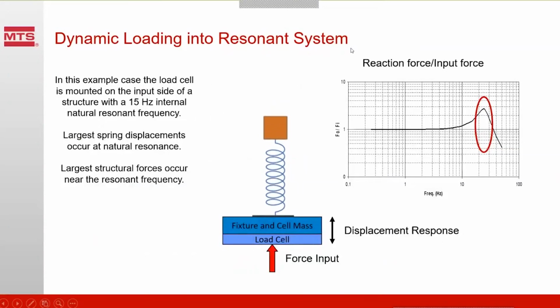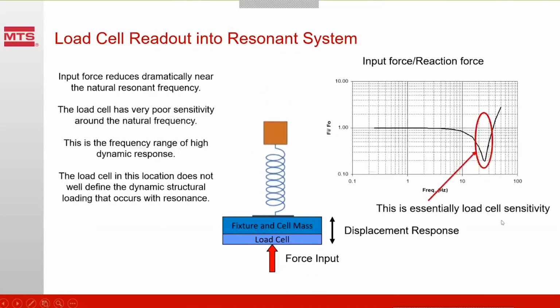Here's an example of a load transducer in a dynamic system. In this case, we've got our simple spring bouncy model. So when we get to 15 hertz, that's the natural frequency in this sample, the amplitude response of the bouncy goes way up higher. You see here. But the load cell down here at the bottom, what does it see? It sees the inverse of that. It says at 15 hertz, I hardly have to provide any force to get lots of output. In other words, the load cell sensitivity is dropping as we get near the resonant frequency. Its sensitivity becomes very low, in fact, to the point where it could give us problems with control.